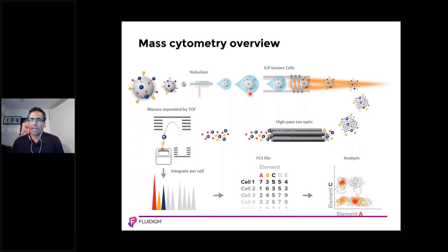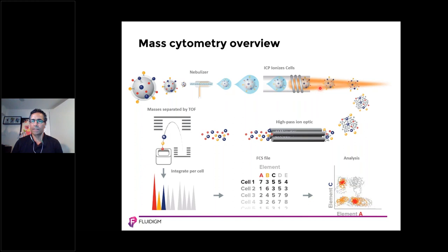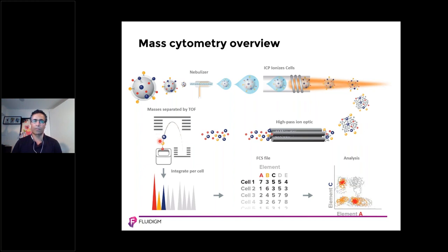I'll give you an overview of how mass cytometry works for those not familiar with the technology. Labeled cells are introduced into the instrument in suspension. Aerosol droplets are formed and directed into the plasma, where the cells are vaporized, atomized, and ionized. Low-mass ions are removed in the high-pass ion-optic filter, resulting in ions enriched for the probe isotopes used for the antibodies. The ion cloud then enters the time-of-flight chamber, where the probes are separated on the basis of their mass.